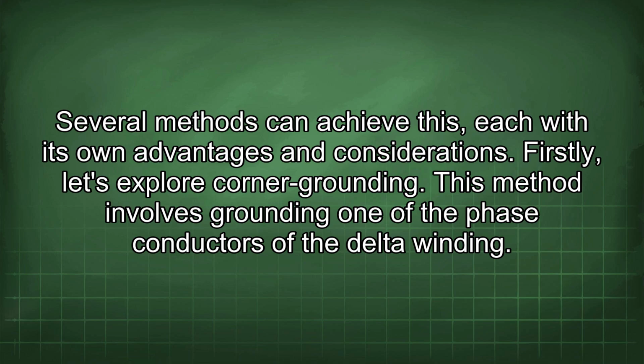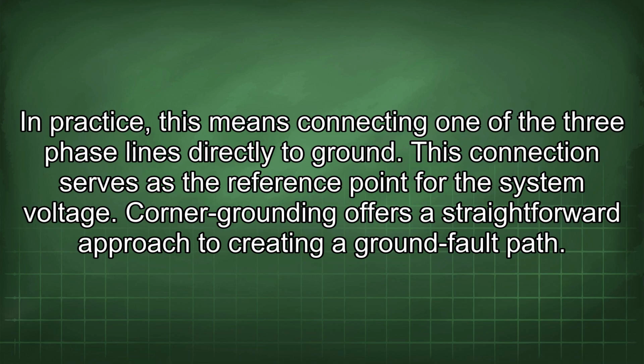Firstly, let's explore corner grounding. This method involves grounding one of the phase conductors of the delta winding. In practice, this means connecting one of the three phase lines directly to ground. This connection serves as the reference point for the system voltage. Corner grounding offers a straightforward approach to creating a ground fault path.